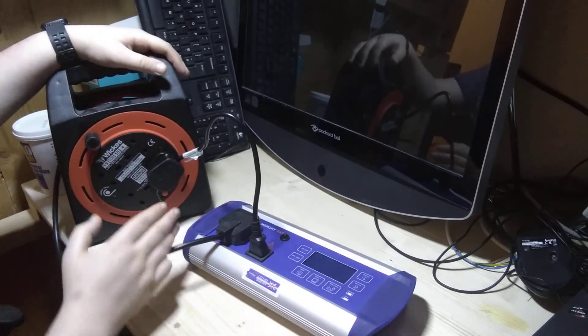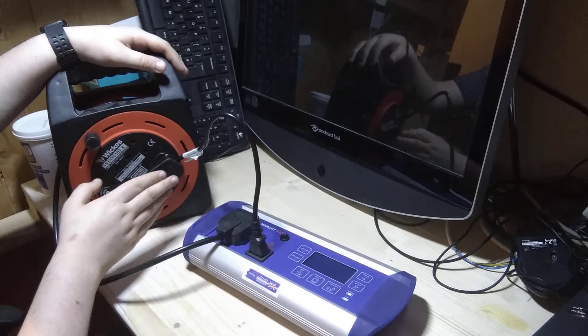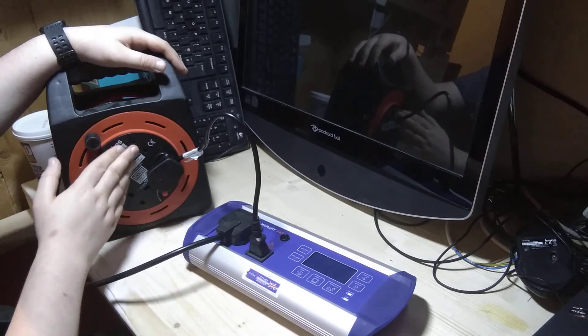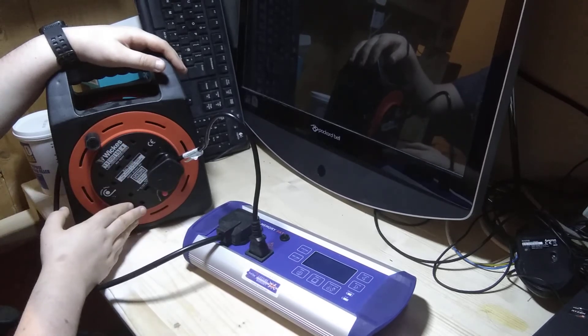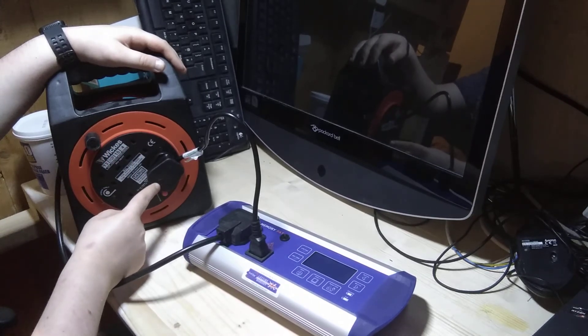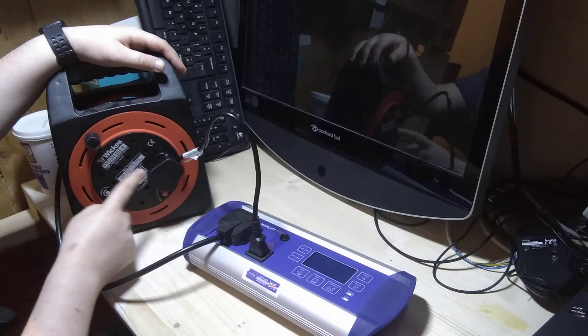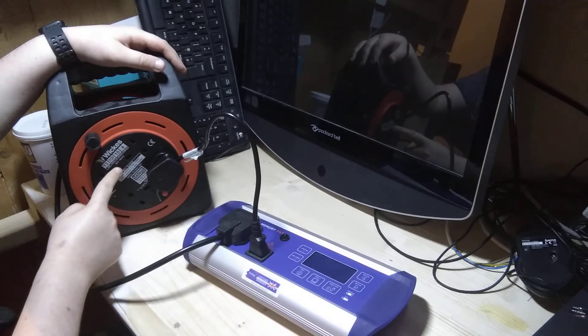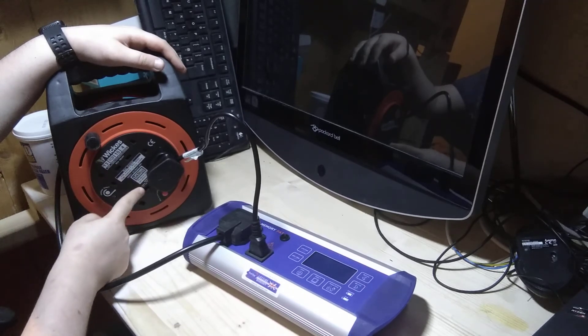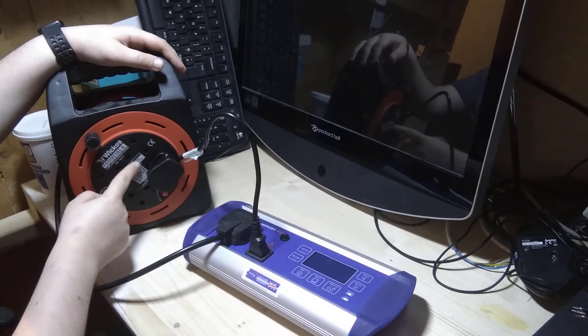Also, to bear in mind, you need to make sure that you've tested each and every socket in case of a poor earth connection. That's the earth connection on the top pin here on each socket.